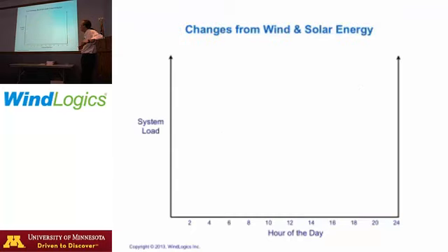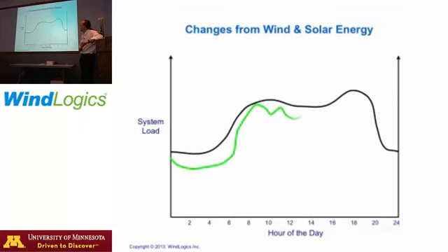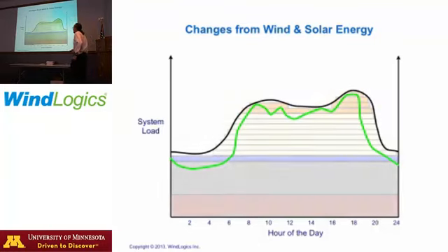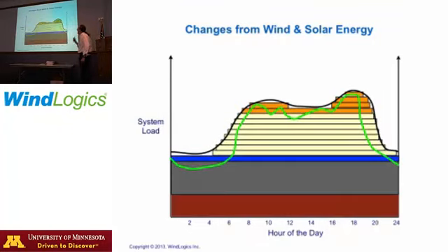So that's great, we're used to that. Very nice plan. So now the same load profile, we just add in a bunch of wind, and we look at the net load that has to be followed by the conventional units. We lay those on here and we say, gosh, what changes here? Well, some pretty big things actually change here. Some of our basically baseload units aren't baseload anymore. They now have to be ramped or even shut down parts of the day. So we might be doing more starts and stops or ramping there.